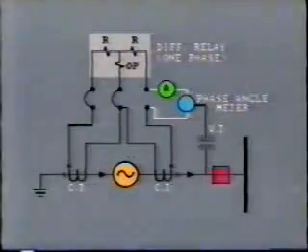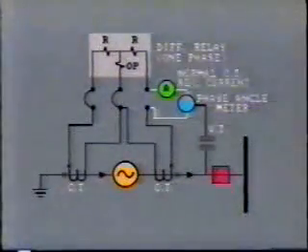With a balanced load on the generator, the current passing through each relay operating coil should be at 0 or a very low value. On the other hand, current measured through the restraint coils should be equal to the CT secondary value. In any particular phase, the current through the restraint coils on either side should be 180 degrees apart. The current enters at one relay terminal and exits from the other. This is correct if there is no internal fault. If the test shows different phase angle relationships, then the CTs have been incorrectly connected. However, this problem should have been discovered earlier by secondary or primary injection tests.